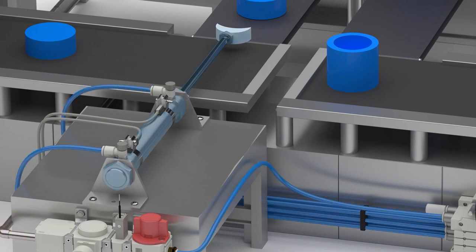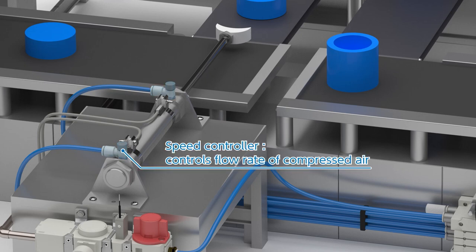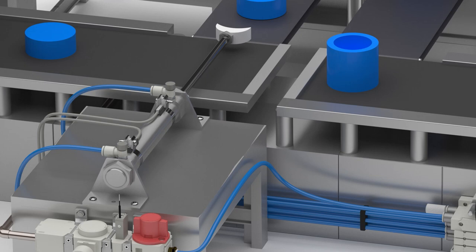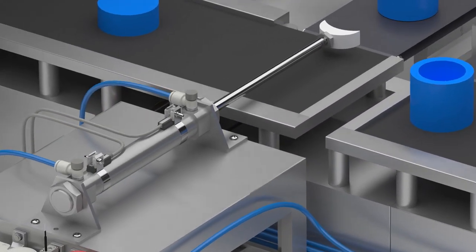The compressed air is supplied to an air cylinder to push workpieces on a conveyor line. The flow rate of the compressed air is controlled by speed controllers, usually mounted directly onto the actuator. Auto switches detect the piston position and send electrical signals to the cylinder control system.